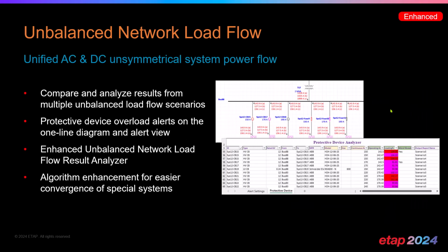We've also enhanced unbalanced network load flow, which is a unified AC and DC unsymmetrical system power flow. We've enhanced it to include an analyzer. This analyzer allows you to run multiple scenarios and then most importantly, compare the results and analyze the results from multiple scenarios all in one table or one spreadsheet. And once you analyze the results, it not only gives you the analysis in terms of the worst case conditions or worst case loading, but it can also give you an overload condition on your protective devices. So this is extremely important to identify if you have a protective device that may not trip because of short circuit, but it may trip because of a sustained power flow that exceeds its overload rating. In other words, it trips on its thermal ratings. And the unbalanced load flow essentially can help you identify those devices so that you can size them appropriately.